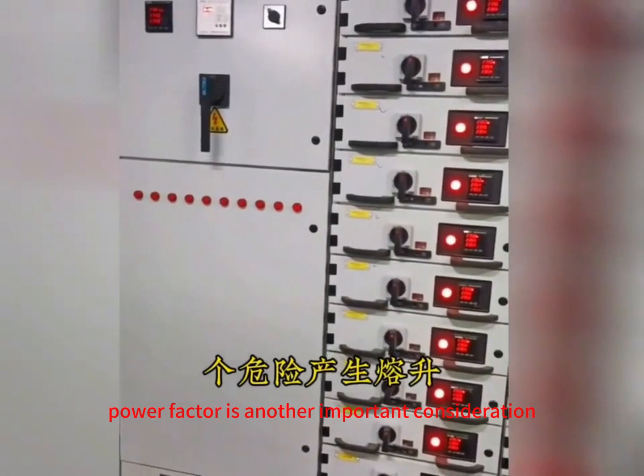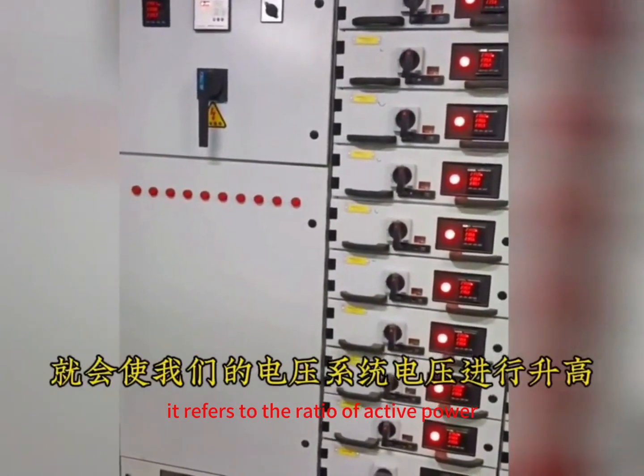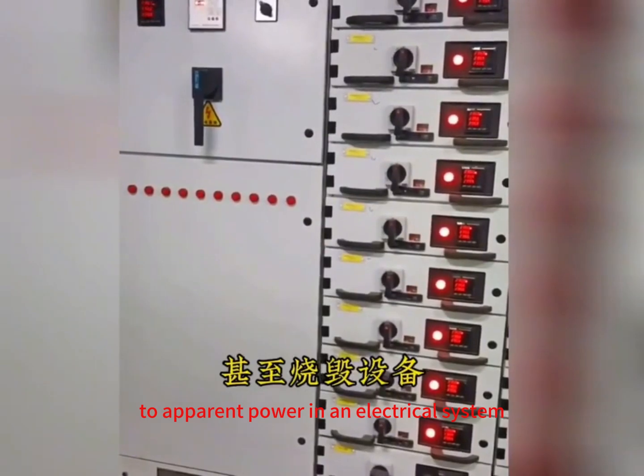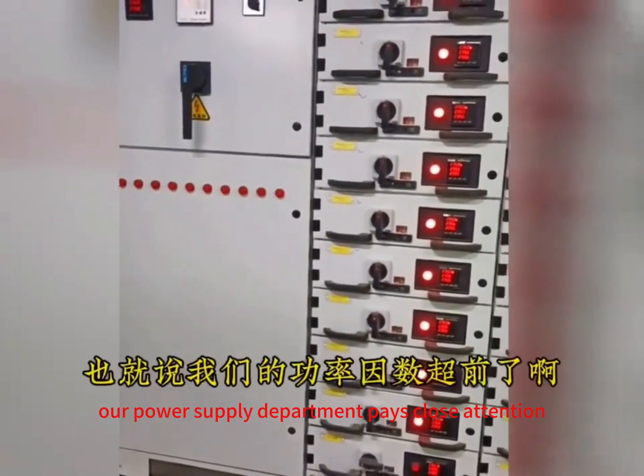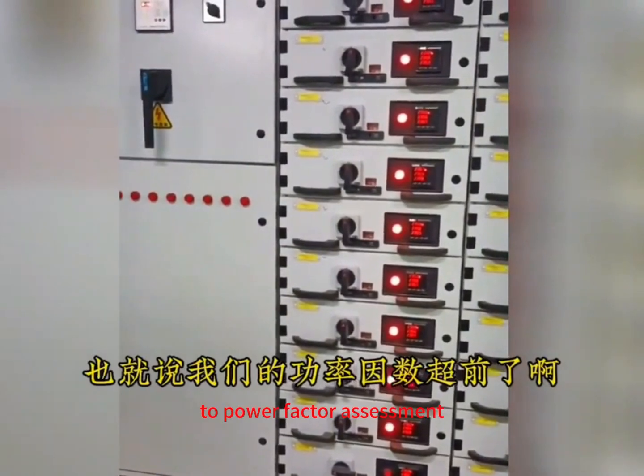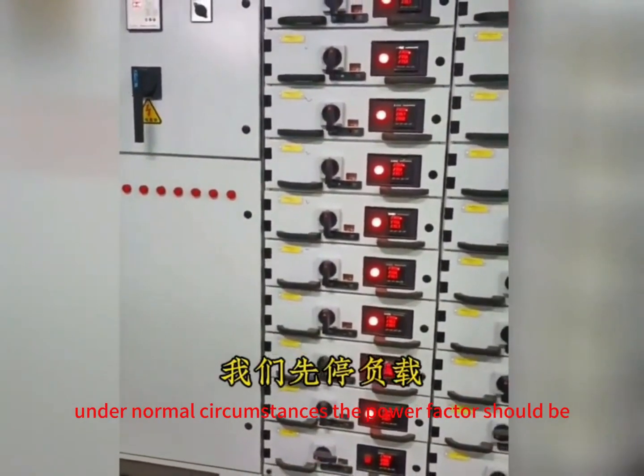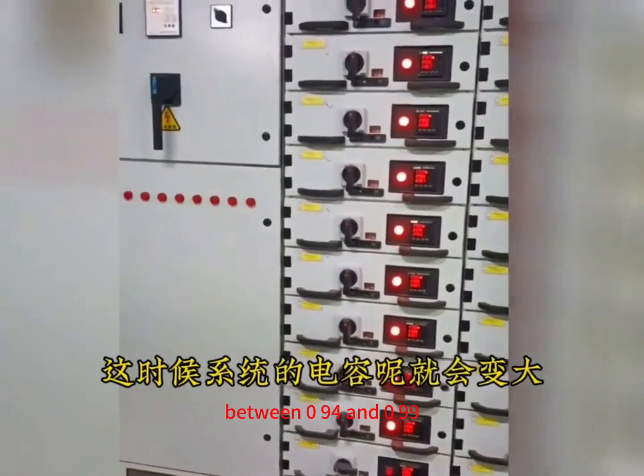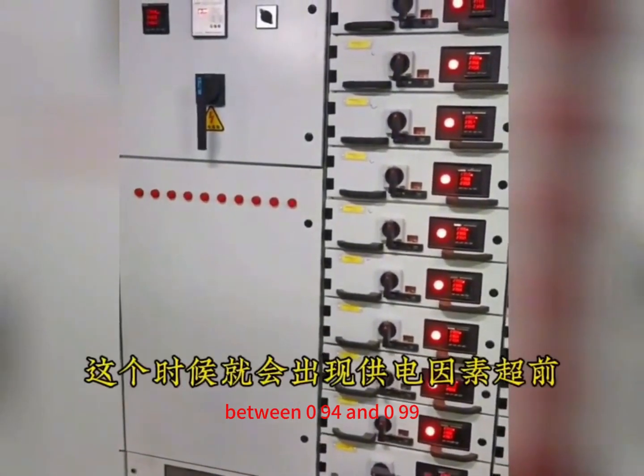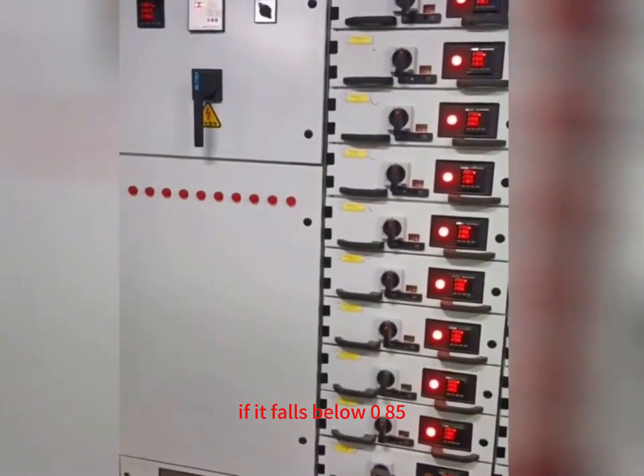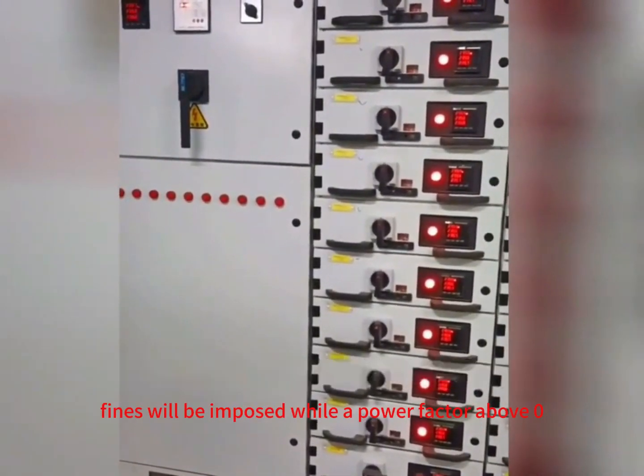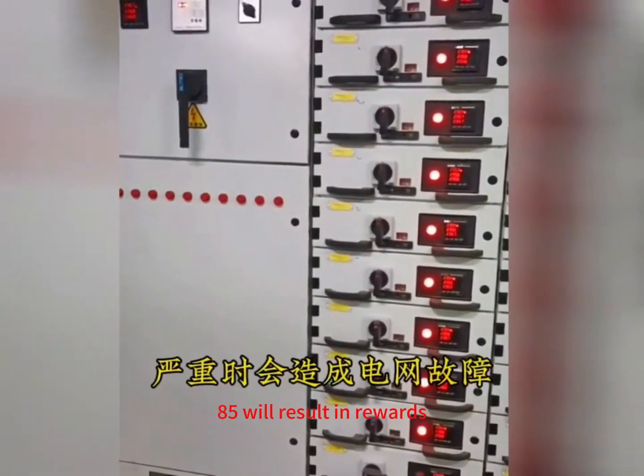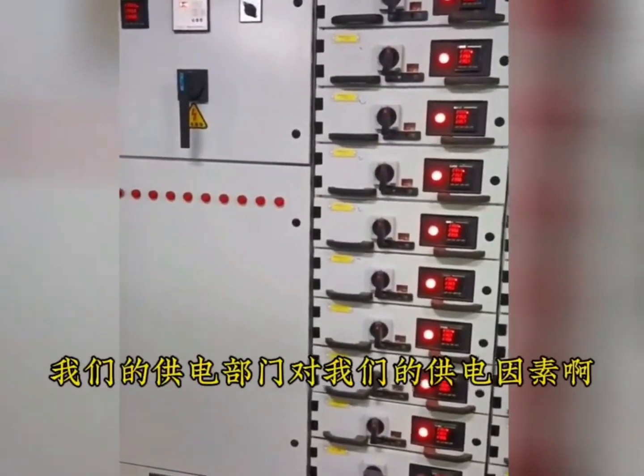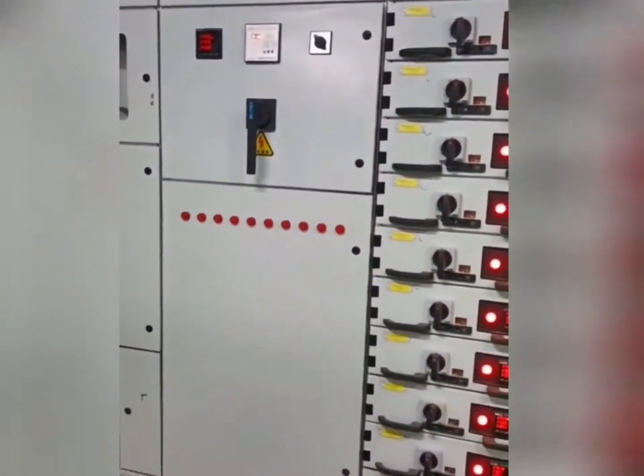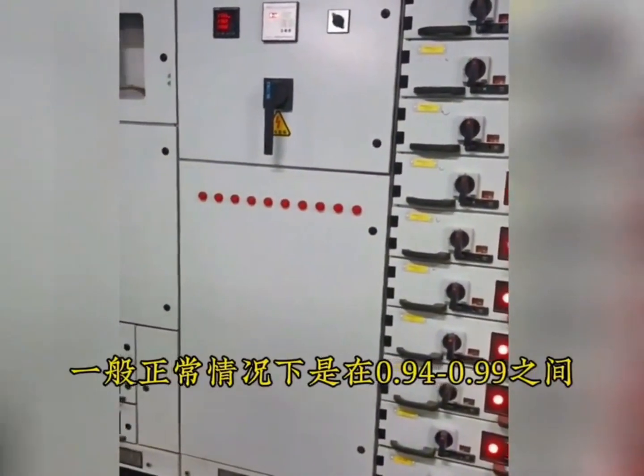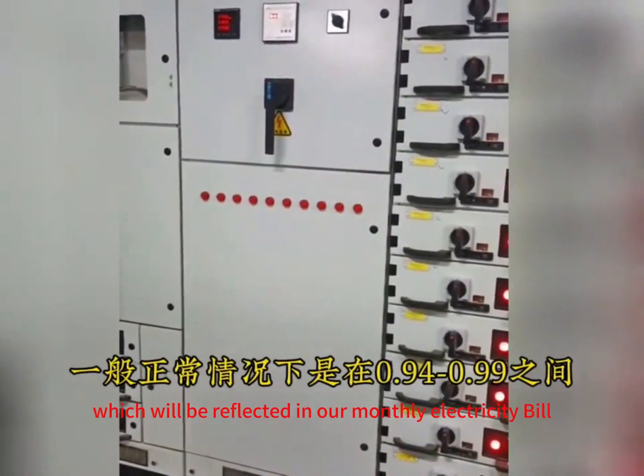Power factor is another important consideration. It refers to the ratio of active power to apparent power in an electrical system. Our power supply department pays close attention to power factor assessment. Under normal circumstances, the power factor should be between 0.94 and 0.99. If it falls below 0.85, fines will be imposed, while a power factor above 0.85 will result in rewards, which will be reflected in our monthly electricity bill.